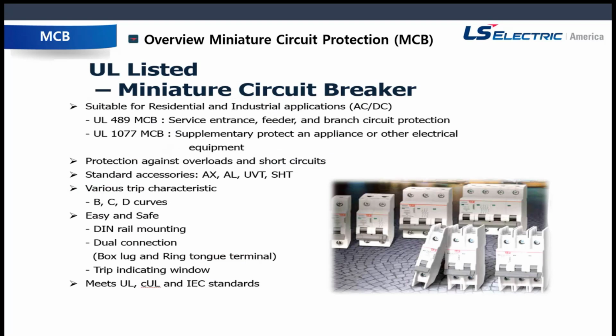So let's talk about the miniature circuit breakers, the UL listed miniature circuit breakers. Those are suitable for residential and industrial applications. They use AC and DC. UL 489 comes with service entrance, feeder, and branch circuit protection, while UL 1077 has supplementary protection for appliances or other electrical equipment. They protect against overloads and short circuits, and come with accessories like auxiliaries and shunts and UVTs.